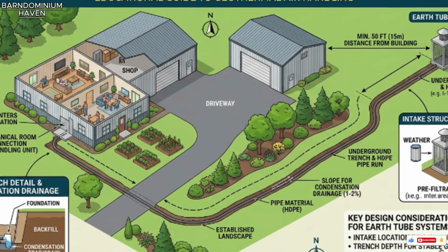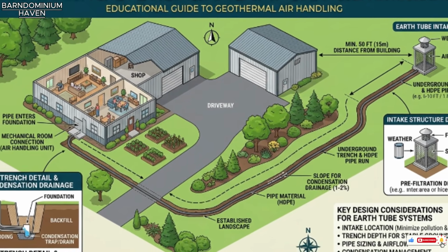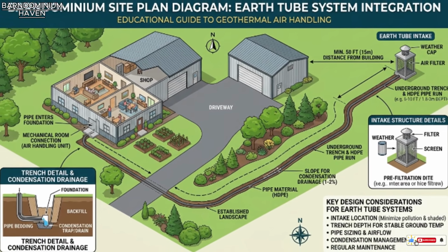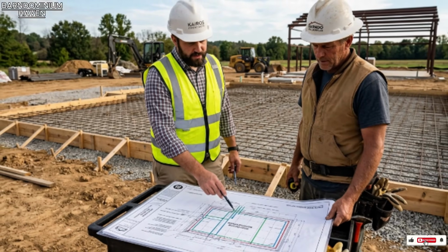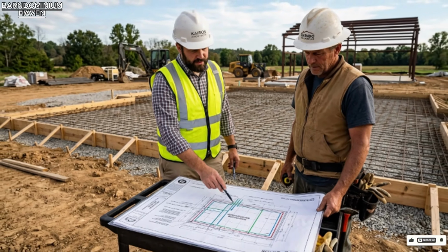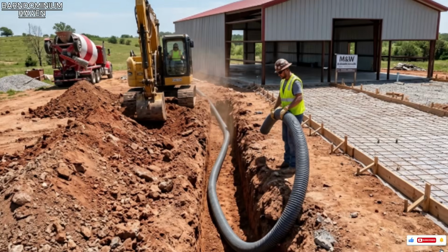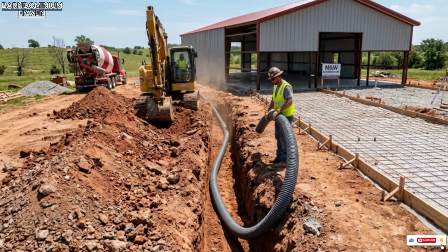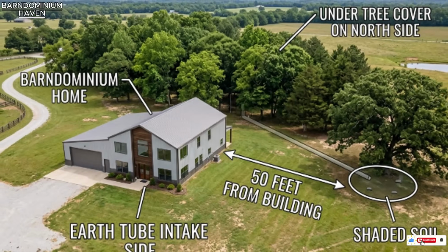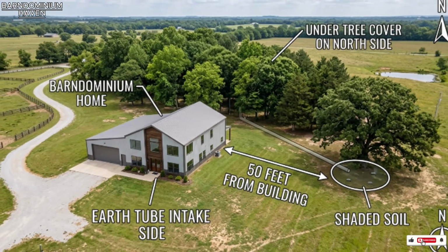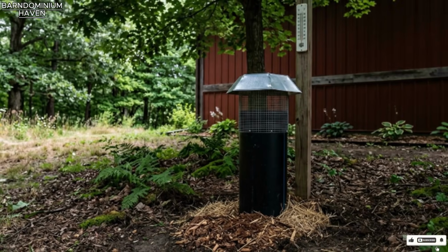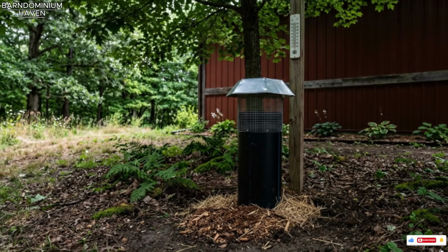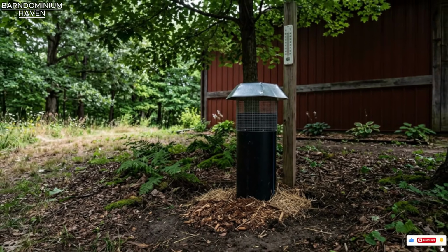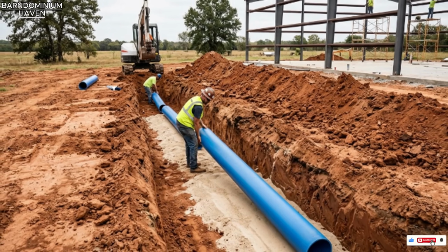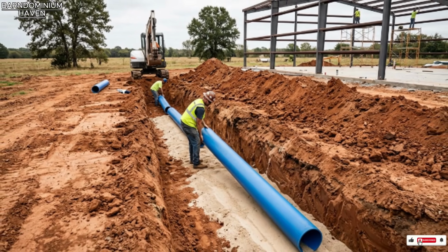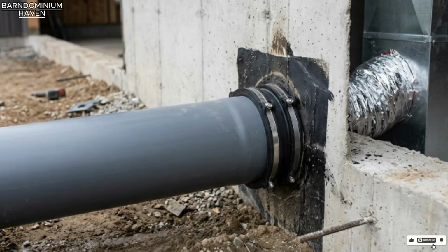The earth tube system is most efficiently integrated into a barndominium when it is designed into the building before the foundation is poured. Not retrofitted after the slab is down and the site is graded. Here is why. The earth tube run, 100 to 200 feet of pipe at 6 to 10 feet of depth, must begin far enough from the building that the pipe's intake is drawing outdoor air from an area whose soil temperature has not been affected by the building's own heat load. A condition called thermal saturation, where the building's waste heat warms the surrounding soil to the point where the earth tube's cooling effect is reduced.